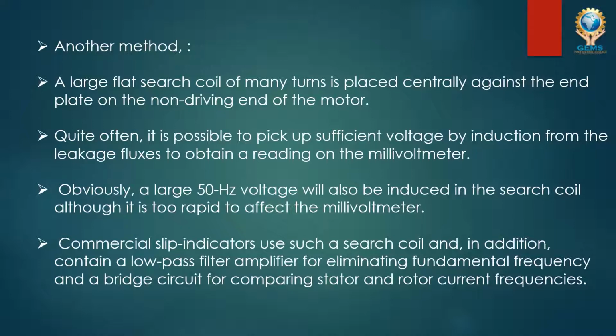If we use a large flat coil with many turns and keep it at the center of the machine, at the non-driving end, since at one end the driving load is connected and at the other end there is no driving load, we can connect this large flat search coil there. When the motor is rotating, just like the rotor EMF, an EMF will be induced in this coil as well.